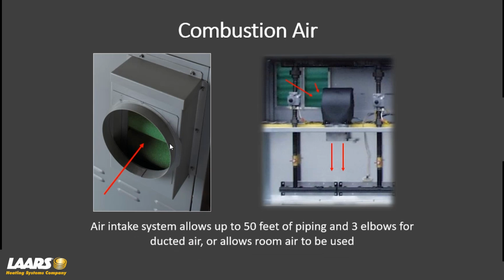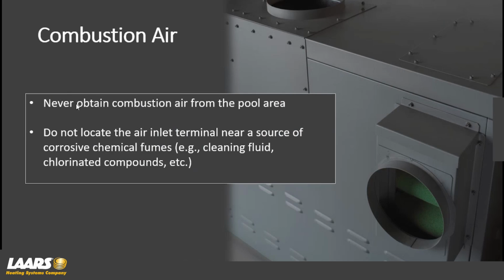Now, air intake, we allow up to 50 feet of venting for combustion air with 3 elbows. Or you could take combustion air right from a mechanical room. So again, we have a collar here, and you can vent combustion air right to the outside. Now, another note I put in here, we've sold a lot of these to hotels. Might be in a mechanical room off the pool area. They've got double doors they leave open. You never want to obtain combustion air from a pool area. And I'm referring to where they're drawing combustion air from the mechanical room, not ducted outside. Obviously, that's going to play havoc on anybody's heat exchanger, burners, igniters, and whatever. So chlorine, any type of corrosive chemicals, rock salt, snow removal, snow melt. You do not want to be drawing that into anybody's combustion or heat exchanger itself.